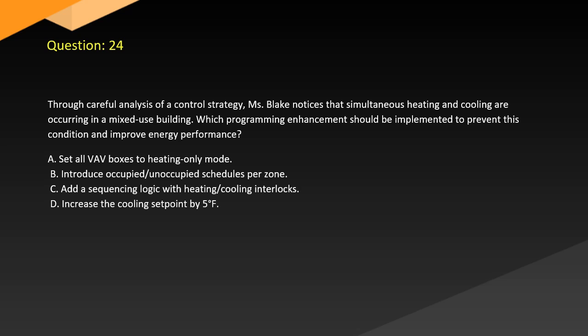Question 24. Through careful analysis of a control strategy, Blake notices that simultaneous heating and cooling are occurring in a mixed-use building. Which programming enhancements should be implemented to prevent this condition and improve energy performance? A. Set all VAV boxes to heating-only mode. B. Introduce occupied and unoccupied schedules per zone. C. Add sequencing logic with heating-cooling interlocks. D. Increase the cooling setpoint by 5 degrees.